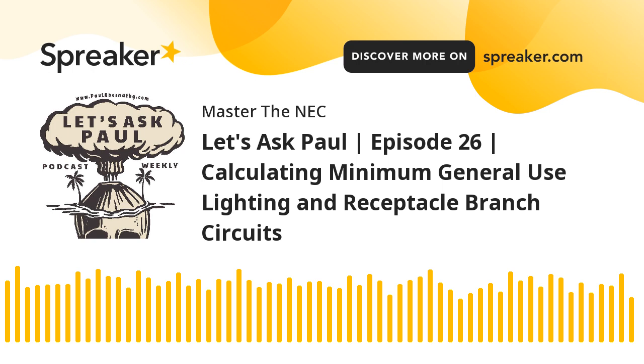So hopefully you got something out of that. That's just a simple question that was asked, how to do the calculation. All right, so let's give you a little bit of something to think about before we end this session. General purpose branch circuits are going to feed things like the lighting and receptacles. Of course, they could feed both. General purpose overcurrent protection shall not exceed 15 amps for 14 gauge, 20 amps for 12 gauge, 30 amps for 10 gauge. All these are small conductor rules in 240.4(D).